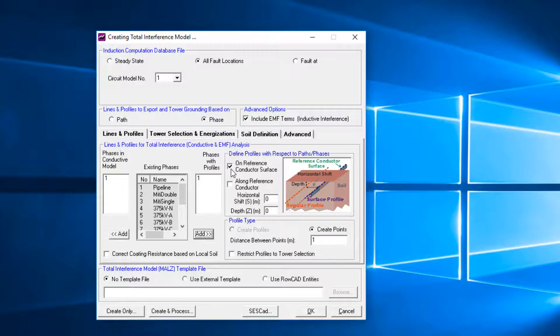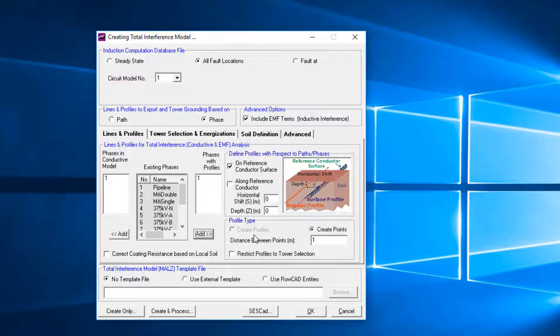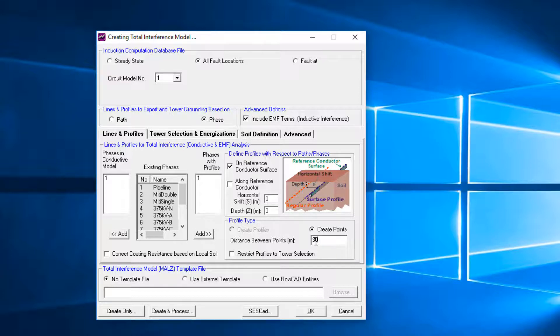Then define the phases that will have observation point profiles, where physical quantities such as touch voltages will be evaluated. Since we want to have the pipeline coating stress voltage in this example, a profile on reference conductor surface is defined. Enter 30 for the distance between points.